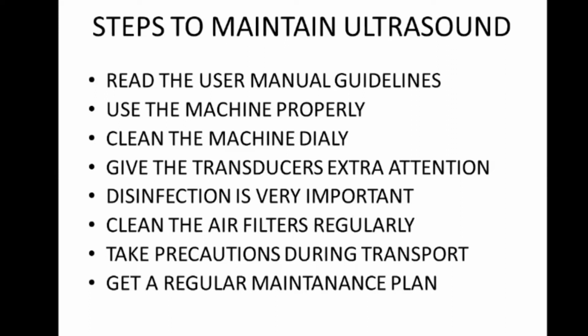And automatically the entire ultrasound system will get damaged. So you should give more attention to that. If the rubber is coming out at the top layer, you should ask the service person to change the layer entirely. Mostly this issue comes only on the convex probe and the cardiac probe, because the usage of convex and cardiac probes is more compared to other probes, and you won't get the layer coming out in the TV probe, ET probe or 4D probe.